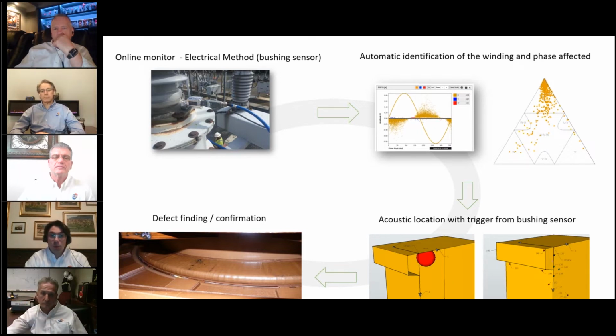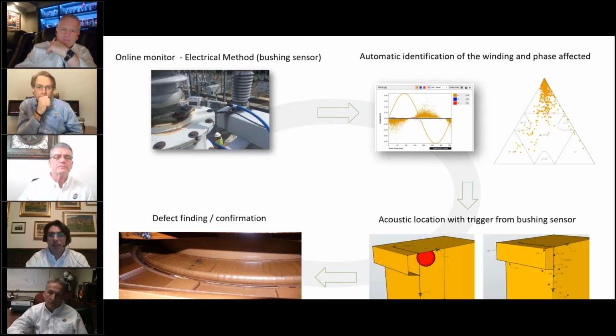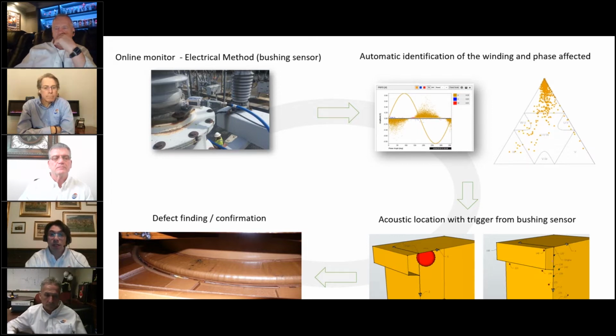And this is extremely helpful, because after that we went in the field with acoustic sensors. It was just off-the-shelf acoustic sensors, not a specific system made by vendors, and we used just an oscilloscope. In less than 2 hours, we were able to locate the source of the partial discharges at the very top of the column and the winding of the phase that was already addressed by the online monitoring system. The defect in this case was on the stress ring, the corona stress ring on the top of the winding. You can see there is some burning trace that was generating the partial discharge, the hydrogen, and also a little bit of acetylene.